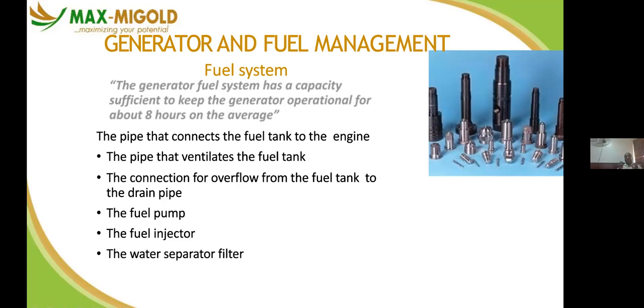The reason for installing a water separator is to do a primary filtration before the fuel filter of your generator. That helps to extend the lifespan of your generator. It doesn't contaminate your injector or the fuel lines. Once you have that, you have done 70% of the filtration before it goes to the generator fuel filter. So it is advisable you install a water separator on your external tank.